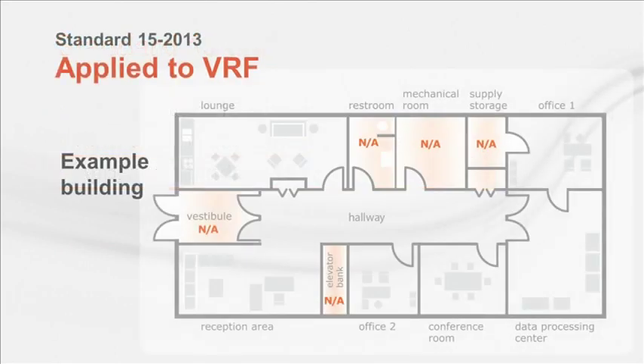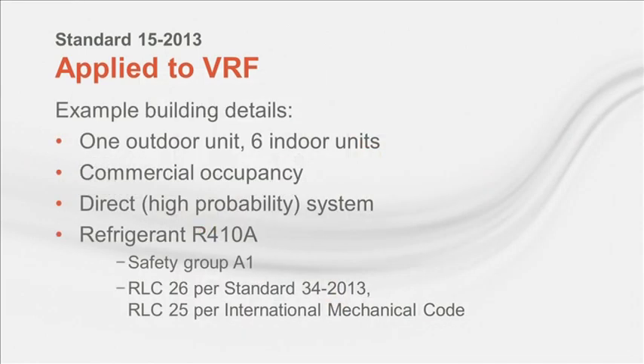The example building is a single-story office with a variety of rooms. All of the rooms, except for those shown in red, are served by our VRF system consisting of 1 outdoor unit and 6 indoor units, 1 per room. The occupancy type is commercial, and it's a high probability system because the refrigerant coil is in the airstream serving the occupied space. The refrigerant is R410A.